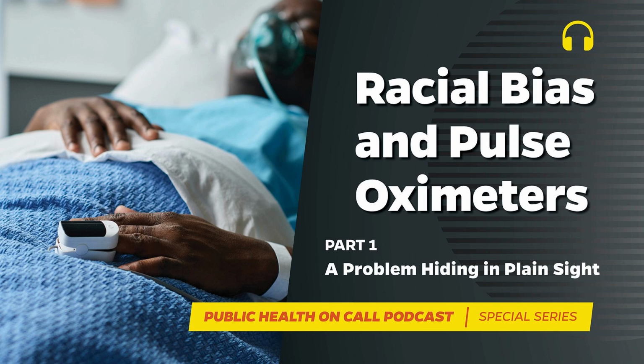One analysis of data from more than 200 hospitals by Nicholas Bosch and Annika C. Law of Boston University found that the vast majority of pulse oximeter usage in hospitals, almost 80%, is outside of operating rooms and ICUs. That is, they're being used where there is no other continuous patient monitoring. According to the soon-to-be-published analysis, in these contexts, there are fewer opportunities to detect and correct for false readings. Pulse oximeters are everywhere, and clinicians are more and more dependent on them to monitor their patients despite their inaccuracies.